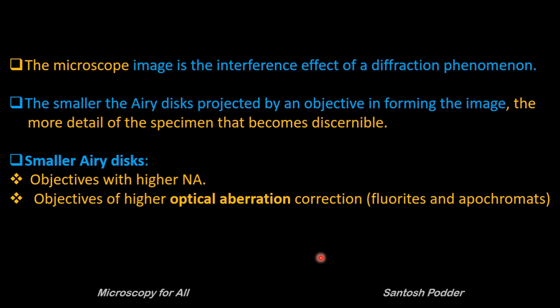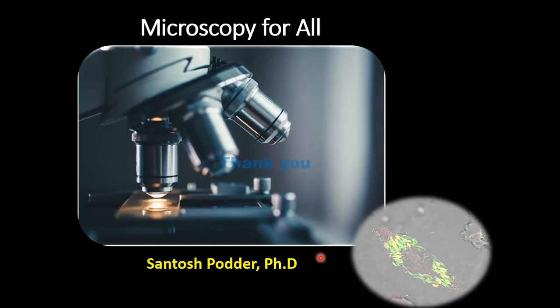To summarize what we learned today: the microscope image is the interference effect of a diffraction phenomenon. Smaller the Airy disc, better the resolution, because more details of the specimen become discernible to our eyes. To get a smaller Airy disc we can use objectives with higher numerical aperture, or objectives with high optical aberration corrections such as fluorites and apochromats. We will learn more about these different kinds of objectives in upcoming videos. Thank you for watching this video — stay tuned for my next videos.